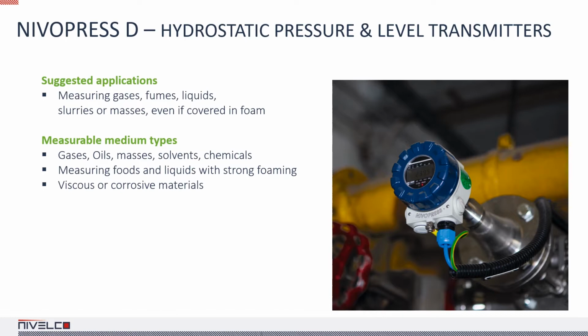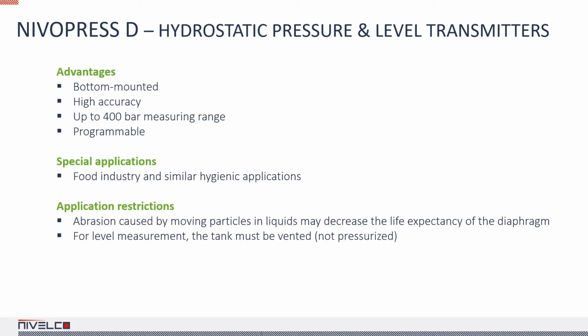The product family includes ATEX certified variants. These devices operate at atmospheric pressure, and they must be mounted at the bottom of the tank. They're highly accurate, and they can withstand process pressures up to 400 bar. Abrasion caused by moving particles in liquids may decrease the life expectancy of the NIVOPRESS D's diaphragm. Therefore, the medium must not contain particulate contamination.